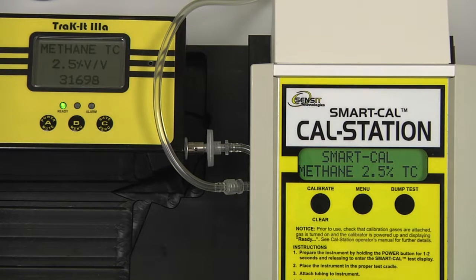The first gas in this case is 2.5% by volume methane, and there will be 2 separate calibrations for both the internal TC and pellistor sensors. On the display of the instrument, we will have a number at the bottom of the screen, which is the raw output of the sensor, and this number is useful as a reference when troubleshooting if any issues should occur. After each successful calibration, saved will be displayed in the instrument, and pass will be displayed on the cal station before advancing to the next gas.